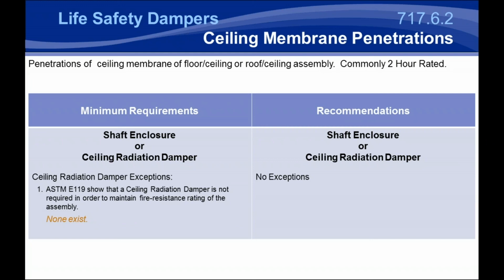When you get into very specific types of floor ceiling or roof ceiling assemblies, you get into combustible wood joist or wood truss applications, or potentially some steel truss applications, where you're only allowed a specific model and manufacturer's product. Basically, because these are combustible applications, they will degrade and need more protection than a regular UL 555C damper. For those assemblies, there's going to be a manufacturer and a model specified, and those are the only components that are allowed in the assembly.